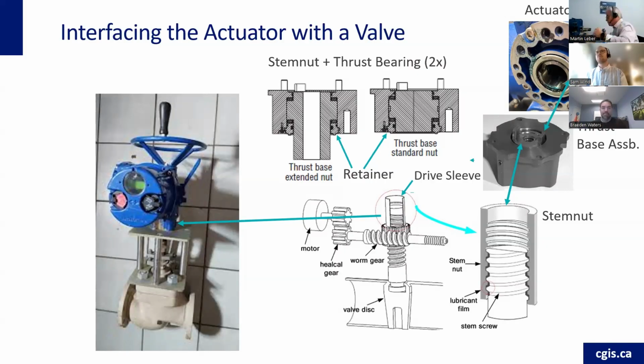Because when sizing an actuator for linear valves, you need to account for not only the torque, but also the thrust it creates when you're lifting and lowering the stem. So the stem nut, this aluminum bronze, is bored and threaded to suit the valve stem, placed into the base assembly, bolted onto the base of the actuator. This whole assembly is put together, then your limits are set. That's a brief overview of how the assembly works.